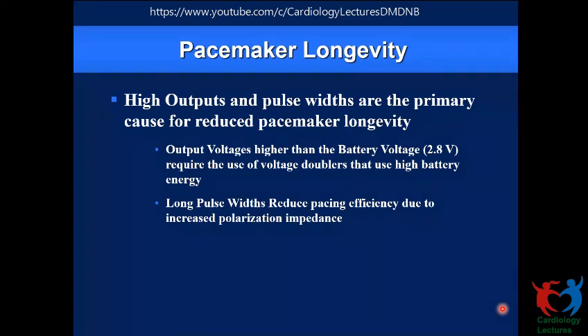Then I may program an output based on 0.7 volt, but that's not the real chronaxy point. Then we need to actually find out. So if time permits, we should ideally get that chronaxy point, the least energy outgo point of a combination of amplitude and pulse width, and program an output based on that, which is not possible in a practical setting. So that is why we can generally think of the nominal setting, which is 0.4 or 0.5 millisecond pulse width. Usually a threshold is under 1 volt, and double the voltage of the threshold as an output is good enough.